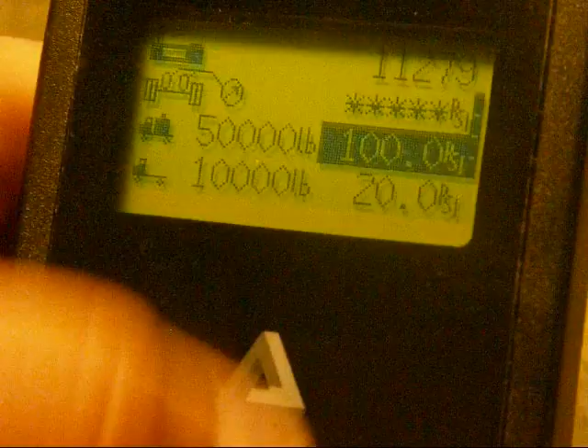You'll notice here that's the number, sensor number. We have all stars here because we're not receiving a signal because I don't have that sensor. It's just a fictitious number I've put in there. So again, we edit the weights, edit the pressures according to what we've recorded when calibrating, and then hit the center button to confirm what we've entered.